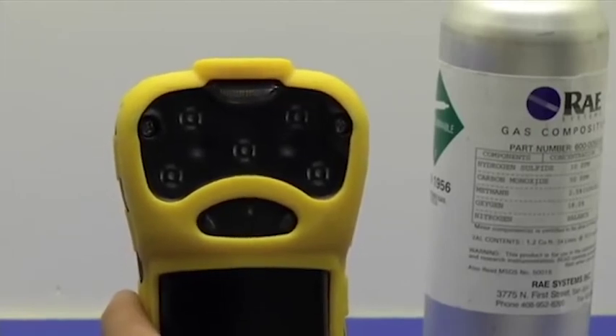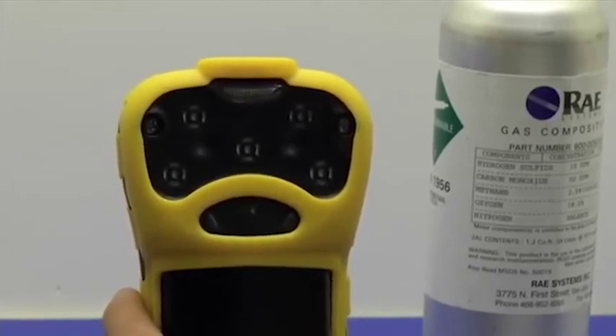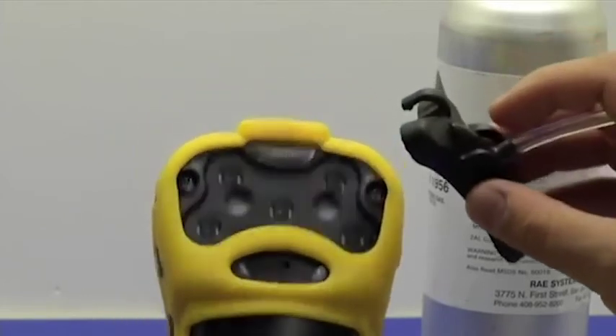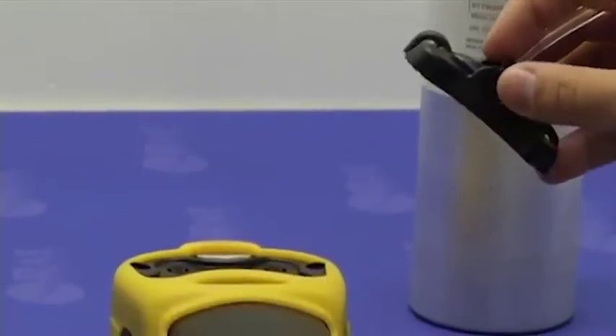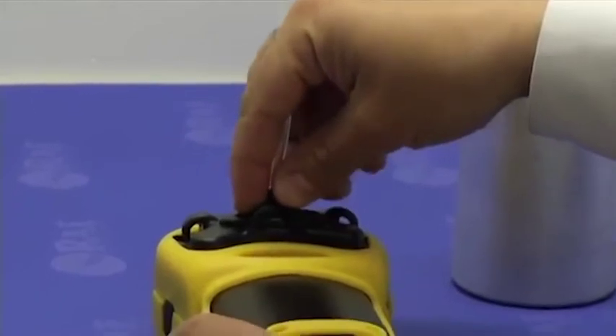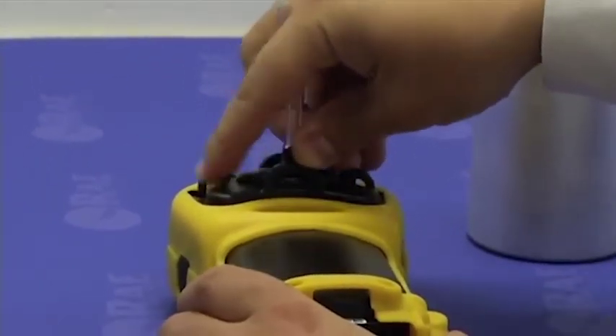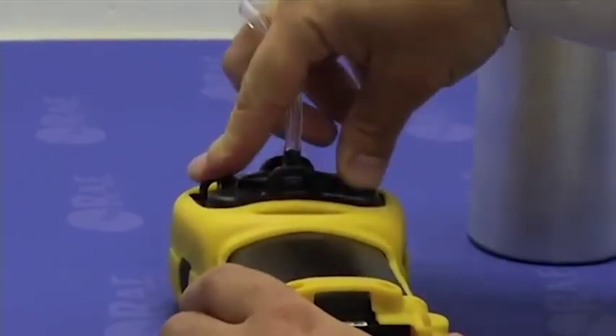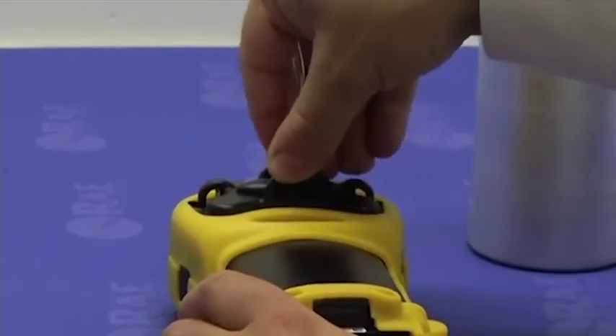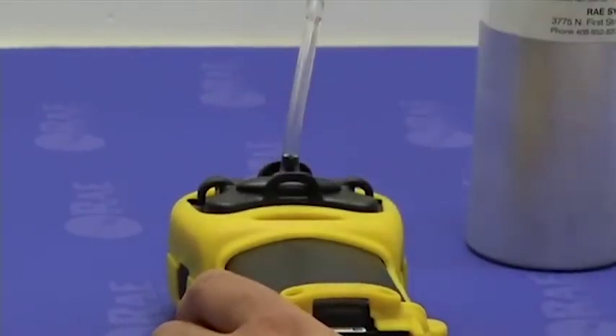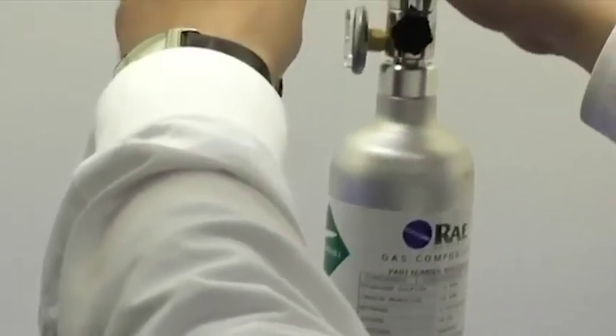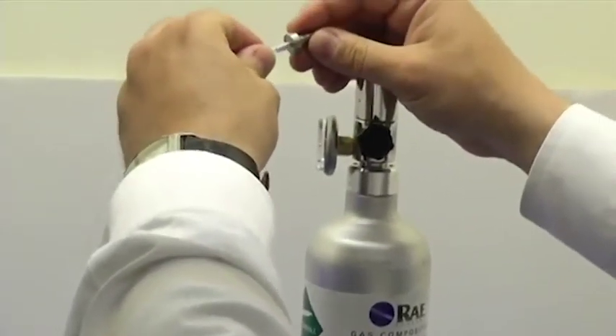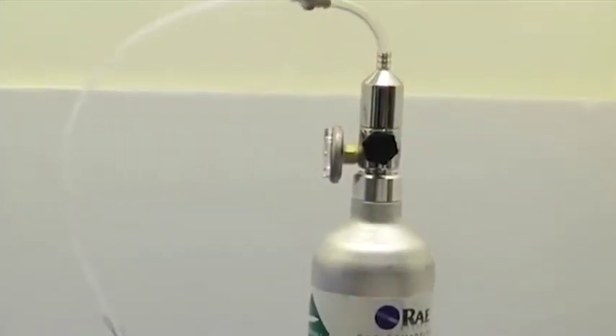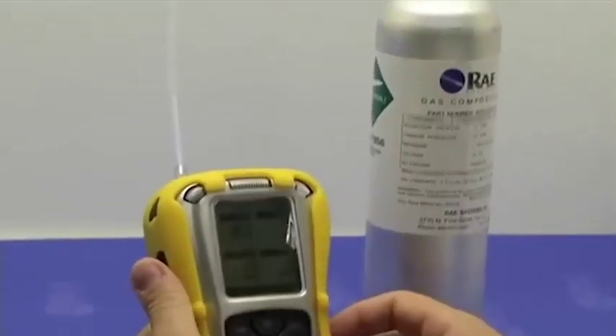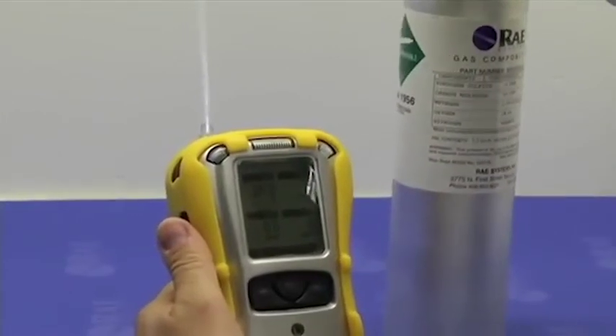Similar to the pumped version, I have to use a calibration adapter when bump testing the instrument. So I'm going to install the calibration adapter, making sure it goes all the way down. I will connect it to the 4-gas mix. Turn it around so that I can observe the screen readings and turn on the gas flow.